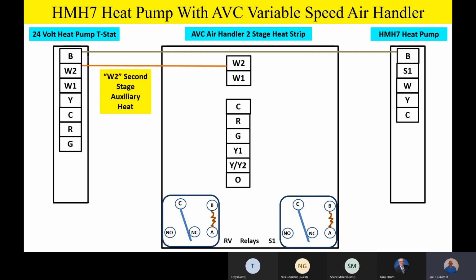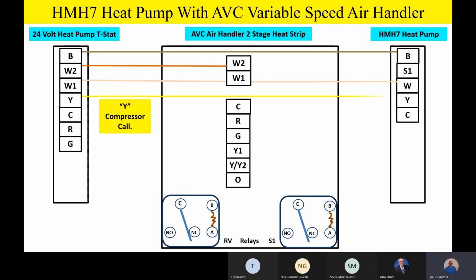W2 is our second stage auxiliary heat, just like we had before. W2 from the thermostat to the indoor unit. W1 is from our thermostat. We go to W1, our first stage auxiliary heat, and we take it right outside to W, because remember, team, that's going to come on during defrost as well. Our Y terminal goes outside, just like we had before, our compressor call.